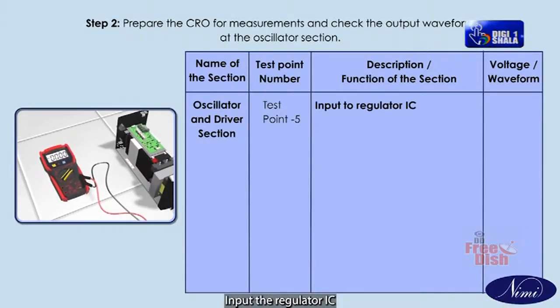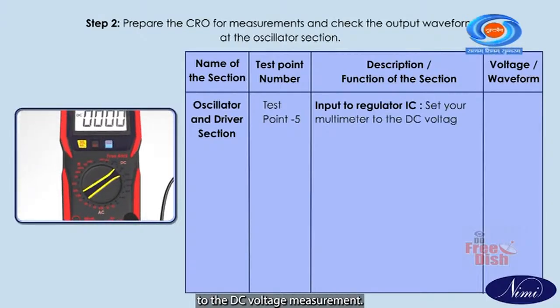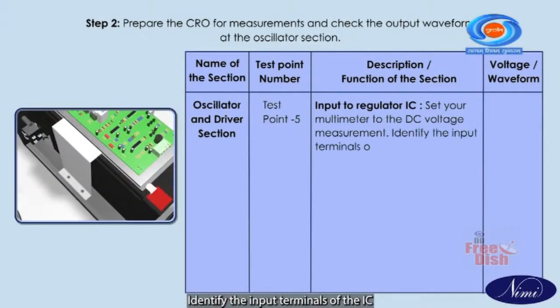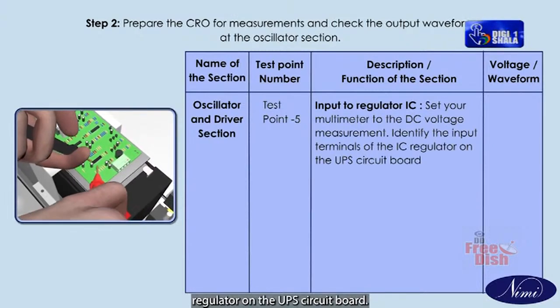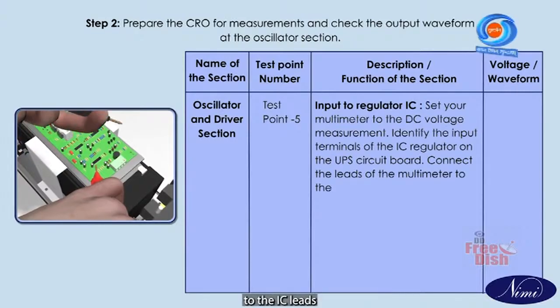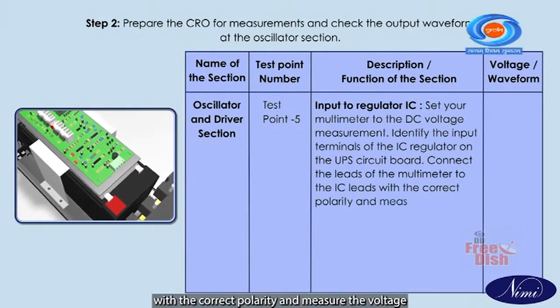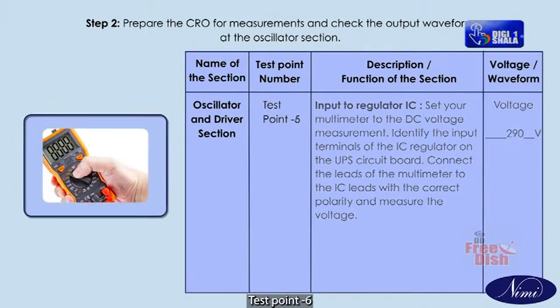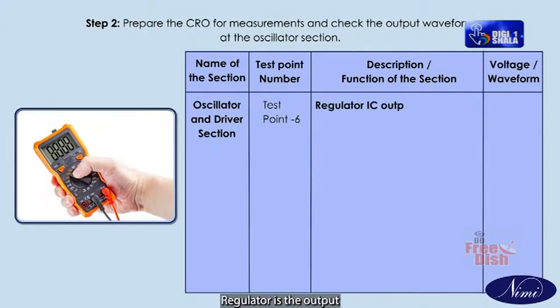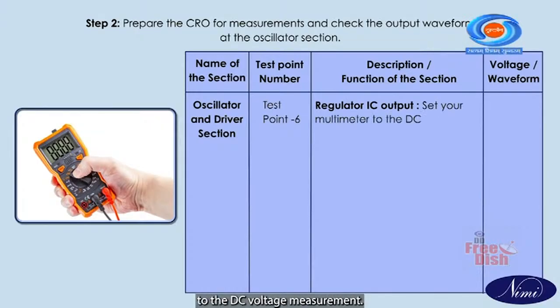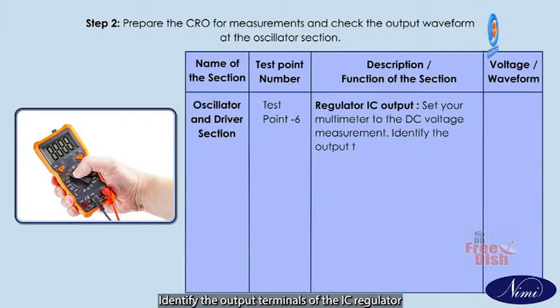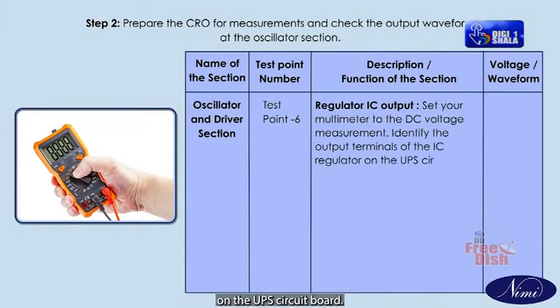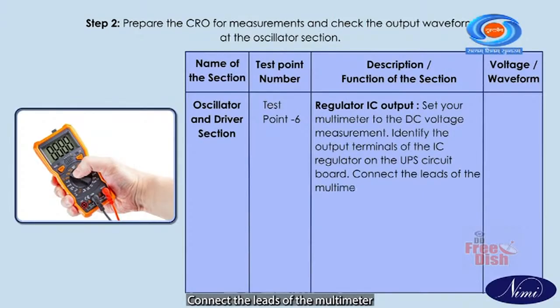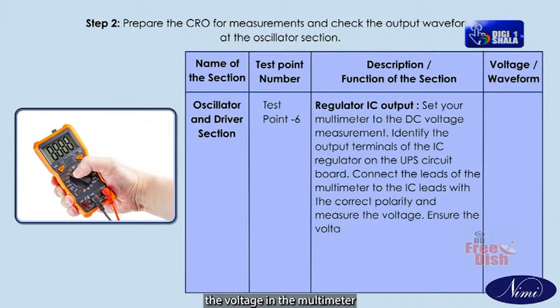Test point 5. Input to regulator IC. Set your multimeter to the DC voltage measurement. Identify the input terminals of the IC regulator on the UPS circuit board. Connect the leads of the multimeter to the IC leads with the correct polarity and measure the voltage. Test point 6. Regulator IC output. Set your multimeter to the DC voltage measurement. Identify the output terminals of the IC regulator on the UPS circuit board. Connect the leads of the multimeter to the IC leads with the correct polarity and measure the voltage. Ensure the voltage in the multimeter is the desired output with a constant.